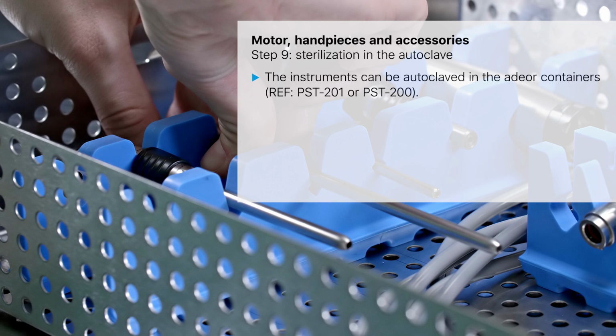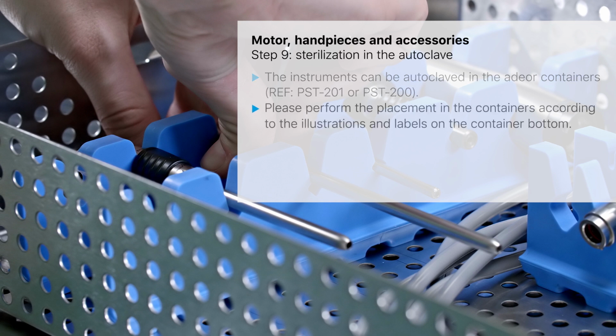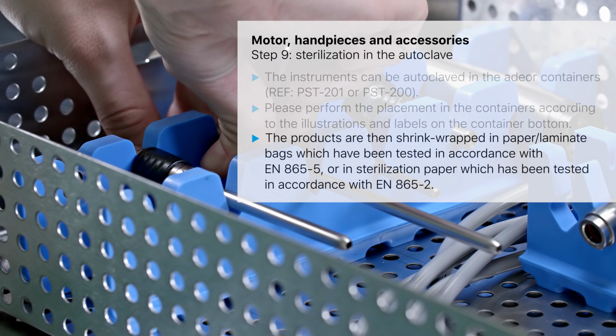The instruments can be autoclaved in the adeor containers, reference PST-201 or PST-200. Please perform the placement in the containers according to the illustrations and labels on the container bottom. The products are then shrink-wrapped in paper laminate bags, which have been tested in accordance with EN 865-5, or in sterilization paper, which has been tested in accordance with EN 865-2.